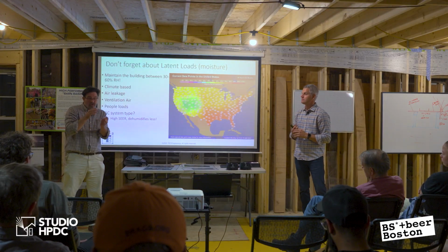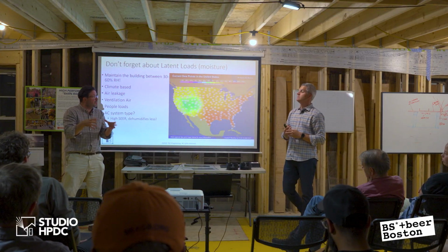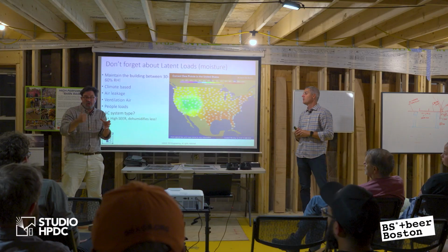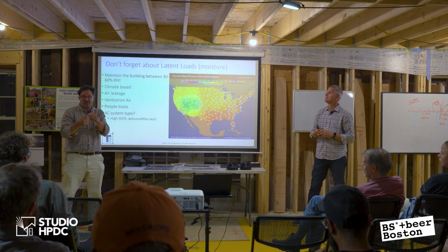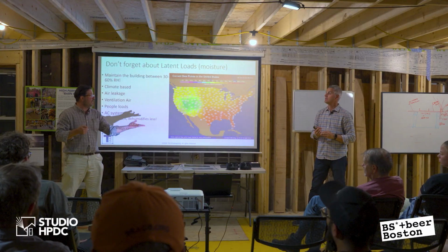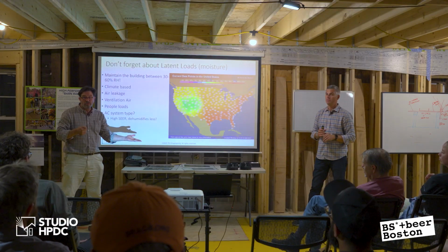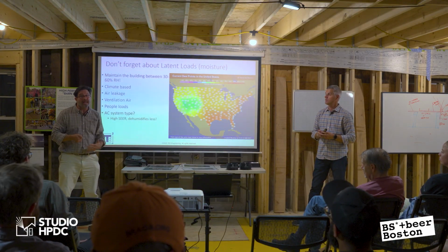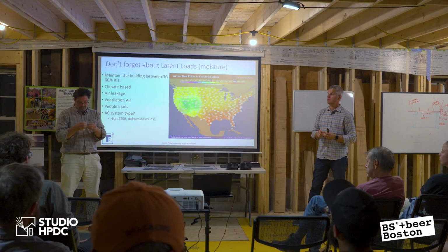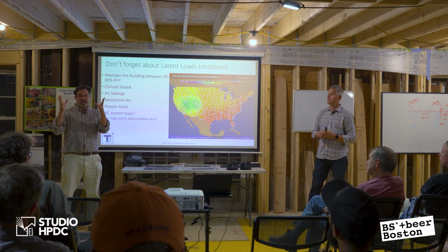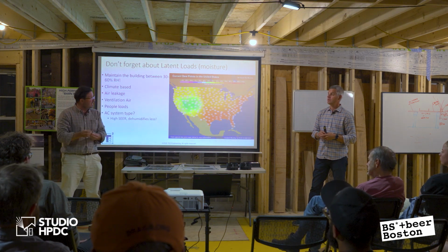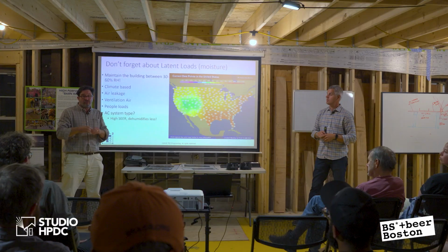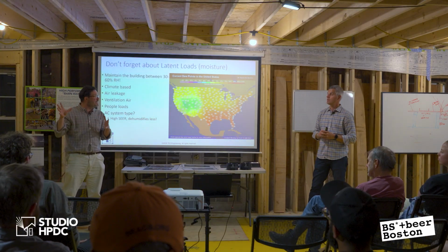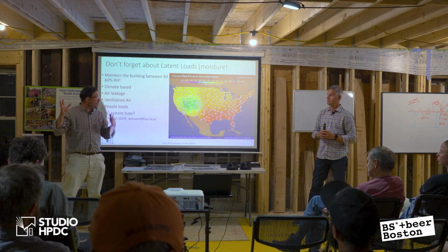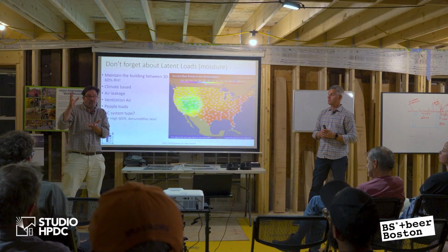So if you take a 211 degree pot of water, right? You add 1 degree, it'll be 212. But to get it to actually turn into vapor, it's another 1,050 BTUs. So it's orders of magnitude greater energy to turn it from water into vapor, and then conversely to condense it back down. So even though there's a tiny bit, relatively speaking, of water vapor, the coil is having to work a lot harder to remove enough energy so that this will settle down and condense.